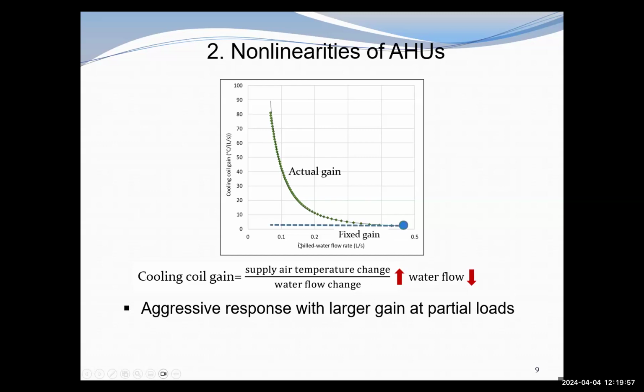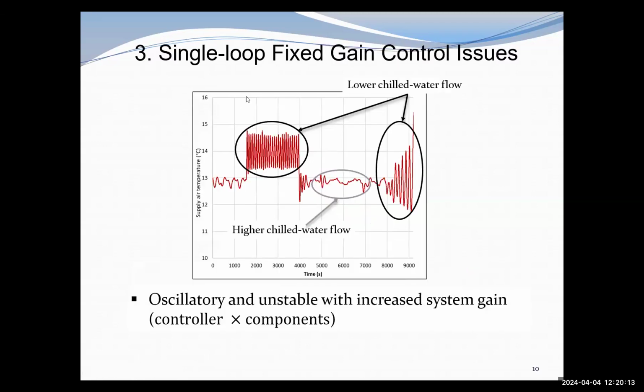So we can see that if the controller is designed by assuming that the cooling coil gain is fixed, but actually the cooling coil gain increases dramatically, then by using this single loop fixed gain control strategy, the system will become oscillatory or even unstable. Here we can see under higher chilled water flow rate conditions, the system is stable and smooth, but under lower load conditions with a lower chilled water flow rate, it becomes fluctuating and even unstable.